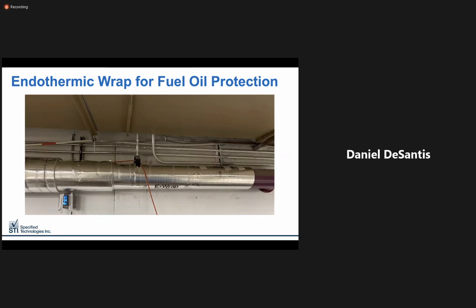We know how effective endothermic wrap can be for the circuit integrity segment, but did you know the same product is tested and listed for the dedicated shaft enclosure of fuel oil piping? In-building fuel oil piping has become increasingly prevalent due to its use in emergency backup generators. Once thought to be limited to hospitals and other public facilities, it is now found in many high-end residential towers, as well as commercial settings around the country. Fuel oil presents a unique challenge, as it is a combustible liquid that needs to be protected under the threat of fire.